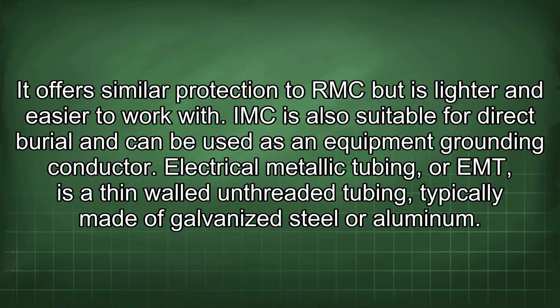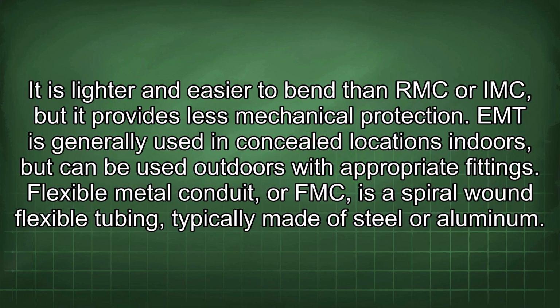Electrical metallic tubing, or EMT, is a thin-walled unthreaded tubing typically made of galvanized steel or aluminum. It is lighter and easier to bend than RMC or IMC, but it provides less mechanical protection. EMT is generally used in concealed locations indoors, but can be used outdoors with appropriate fittings.